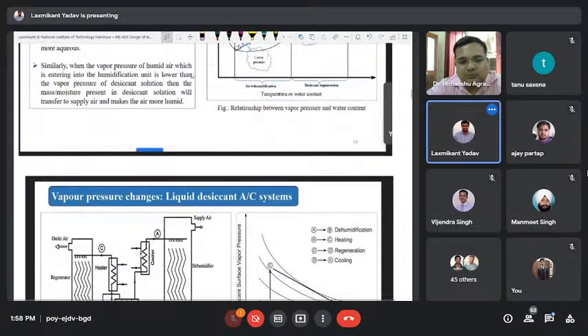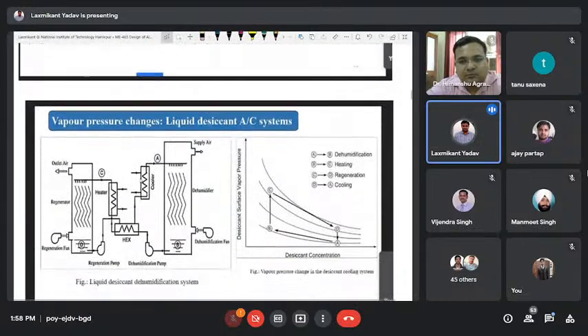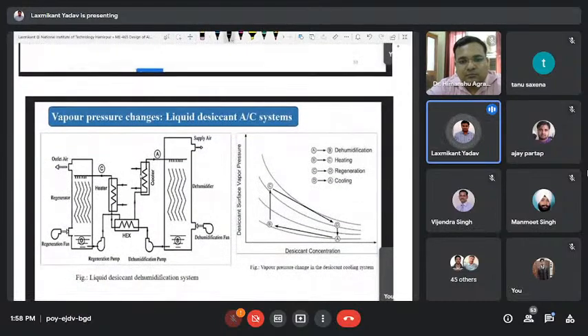Next, this also represents the desiccant surface vapor pressure diagram. So you can see A to B. A to B is the dehumidification, so this is basically the dehumidification chamber. There will be a decrease in desiccant concentration because there will be absorption. So the desiccant concentration changes from A to B, and B to C, where is B to C?